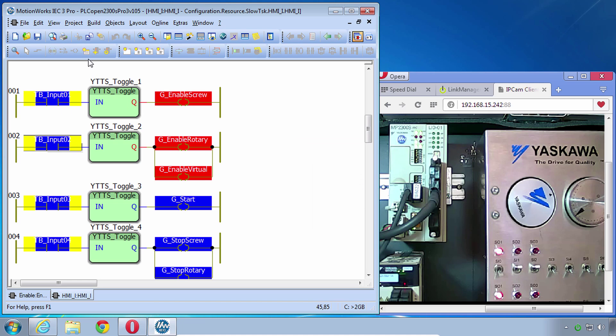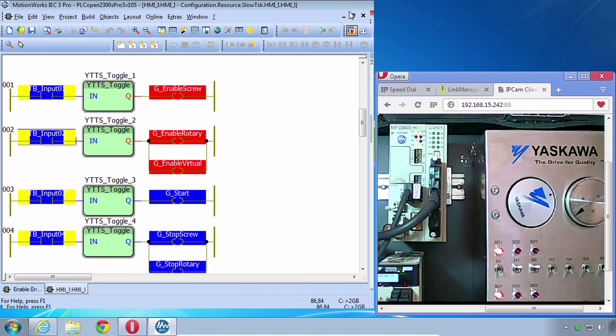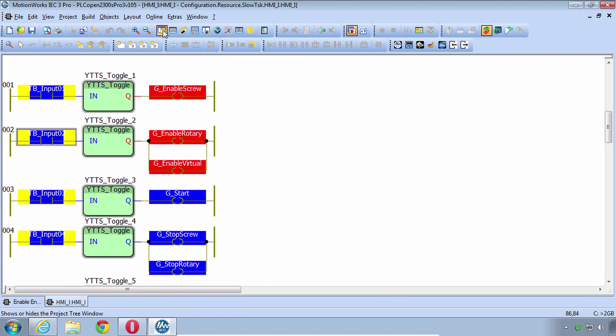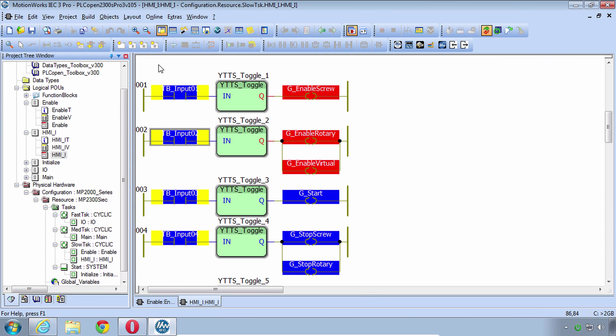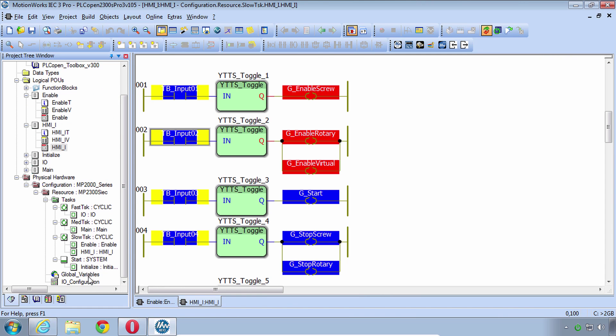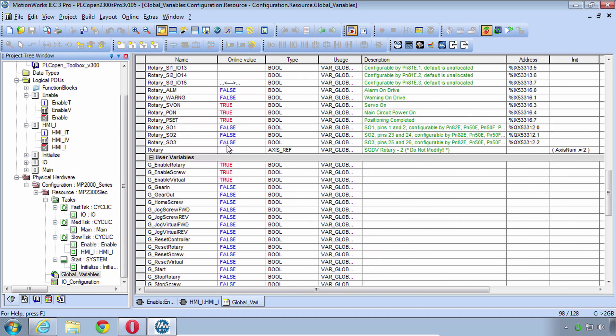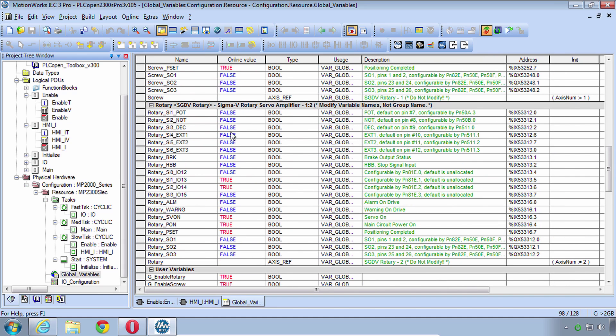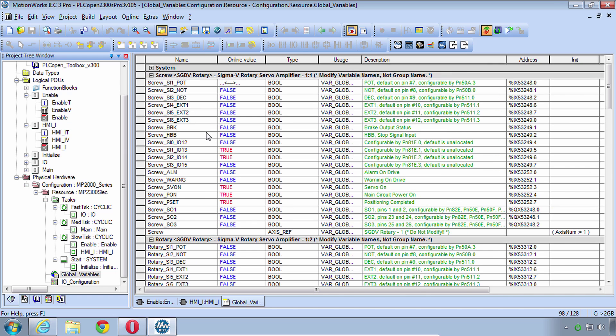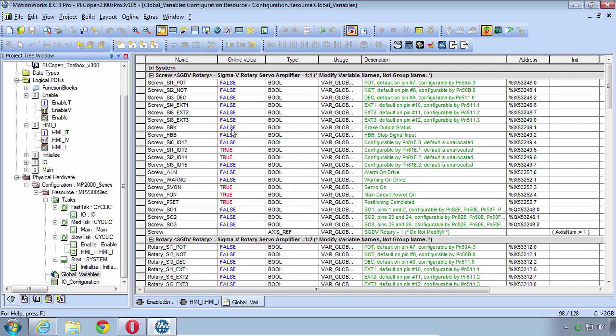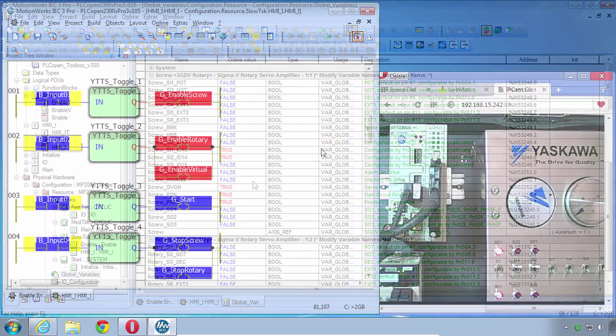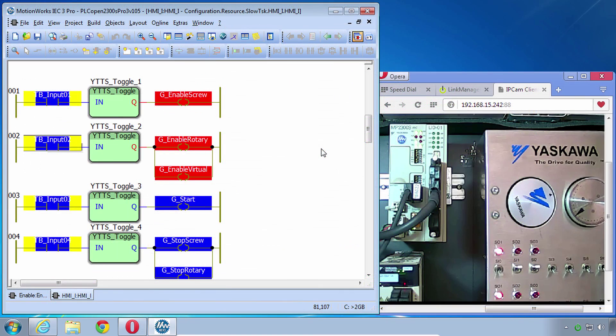And now one final feature that is not so much PLCopen but rather hardware based is if you look at your global variables, each piece of hardware does have some feedback and some of them are related to servo on. For example I can see here that this screw has a servo on input. This is a status input coming back from the servo into the IEC controller. There's also useful information like the power's on, the main circuit power, positioning complete, hardware base block, there's no E-stop on and we mentioned the brake output status. This is a way to get that into your program. So all these signals can be used to make a more robust servo on that checks for these conditions before attempting to use the MC power block. So this is success, we have the servos on.